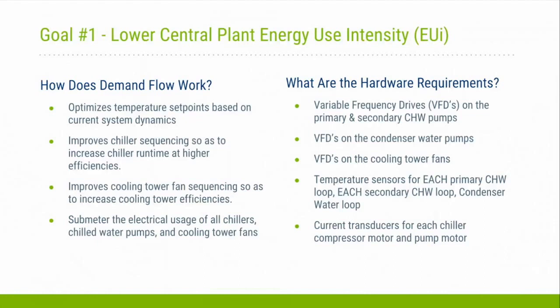And lastly, we submeter electrical usage to provide demand flow the inputs it needs to make decisions in real time. And as Ron mentioned, we added quite a few variable speed drives, for the primary and secondary chill water pumps, condenser water pumps, tower fans, and of course temperature sensors. Some of those were new, some were not new. We just had to replace them. And then lastly, current transducers for the chiller compressor motor and pump motors.